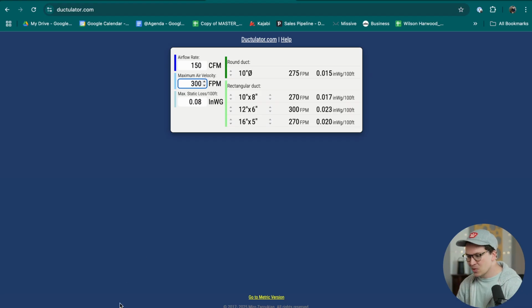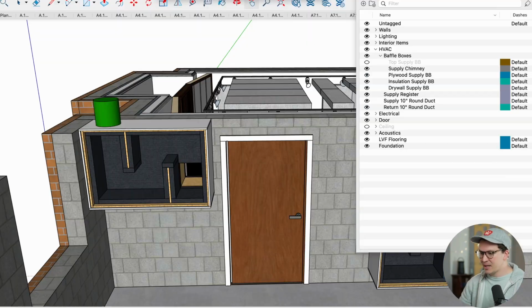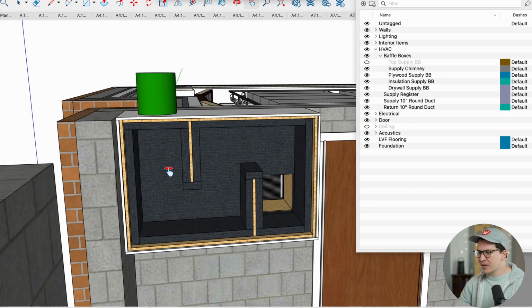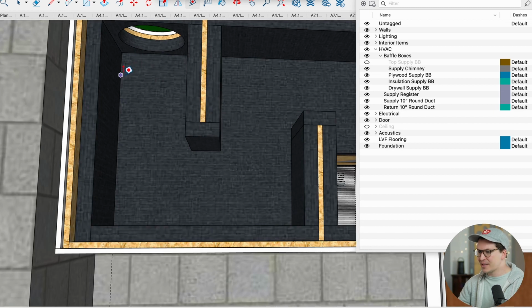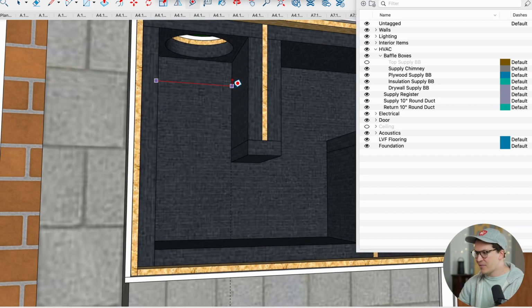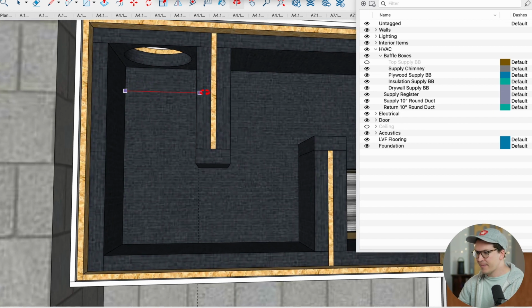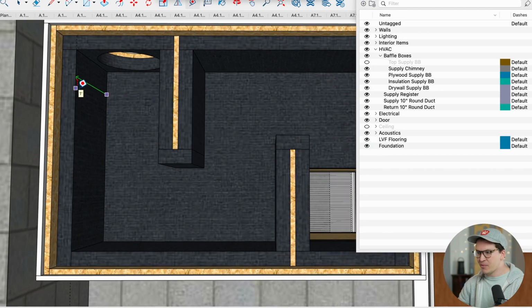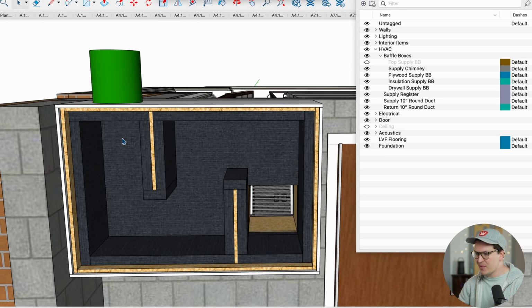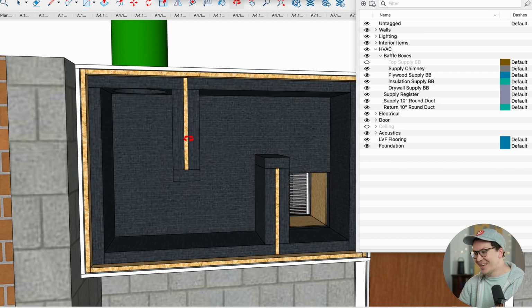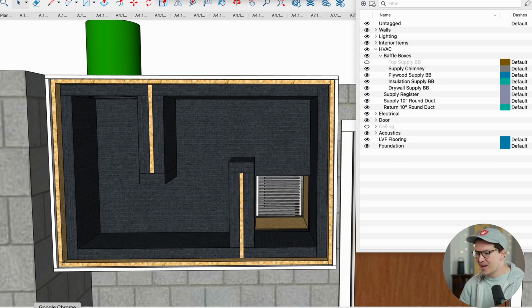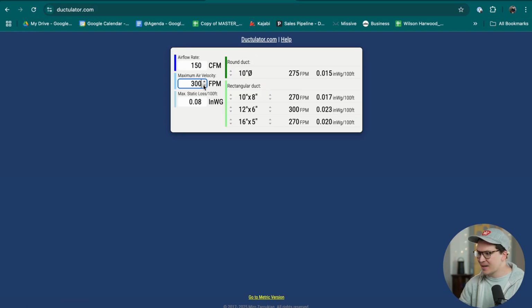Now, if we go back to the original baffle box design that I did in the studio, we can calculate the square duct size that I created. So we have 1 foot going this way, and then for the height, we have 1 foot. And this is pretty typical of my baffle box designs. If I have the space, I'm going to do a 1 foot by 1 foot duct if I can get away with it, or even bigger. Because if we go back to the Ductulator, let's say we did 1 foot by 1 foot. So I'm going to change this to 12, and I'm going to change that to 12.